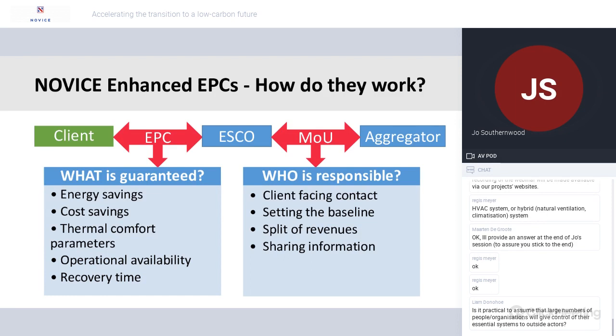What we decided is that while you can't guarantee the revenue stream, you can guarantee things like the thermal comfort parameters. For example, if the building typically operates between 19 and 21 degrees under normal conditions, the EPC might include a clause allowing that range to drift, say between 18 and 22 degrees during a demand response event, giving extra flexibility while still providing a level of performance guarantee.